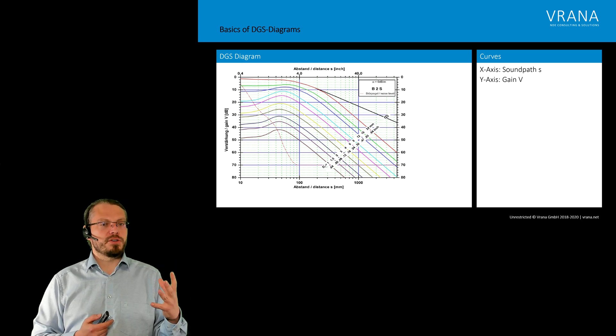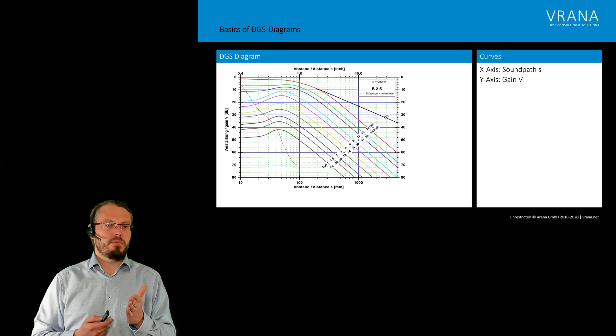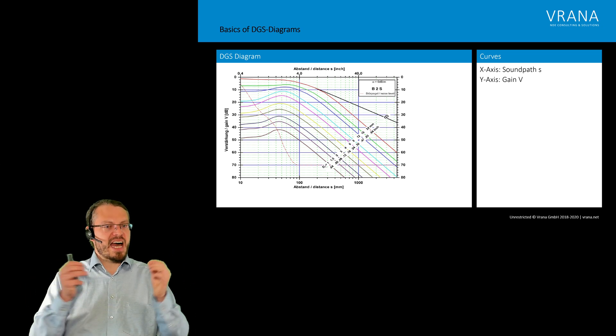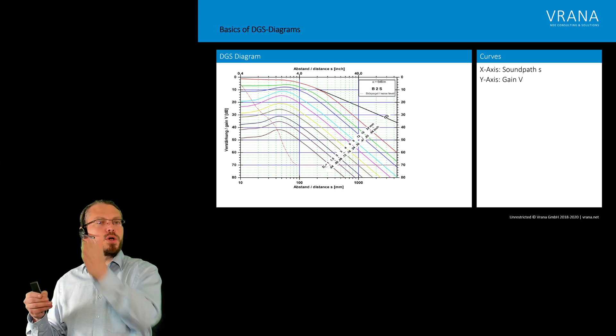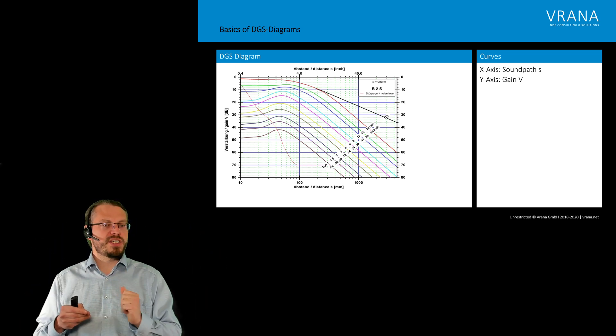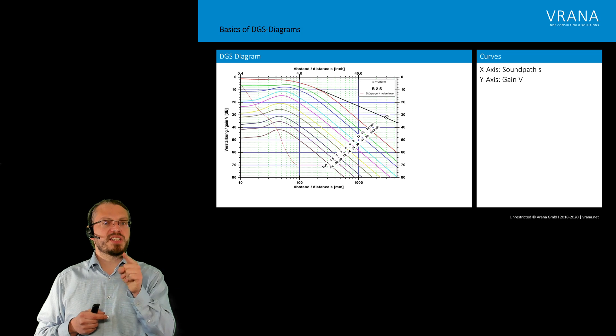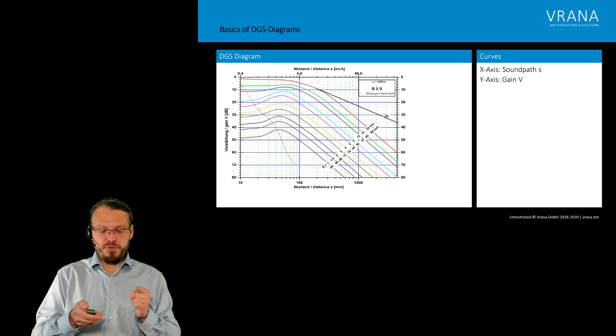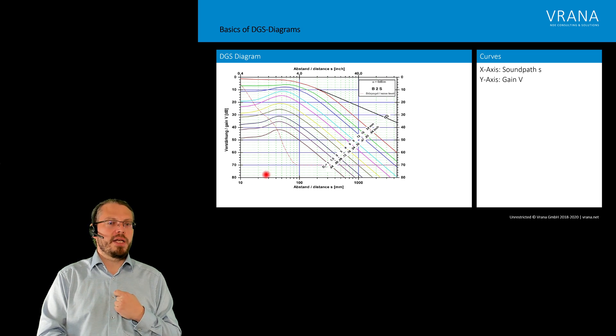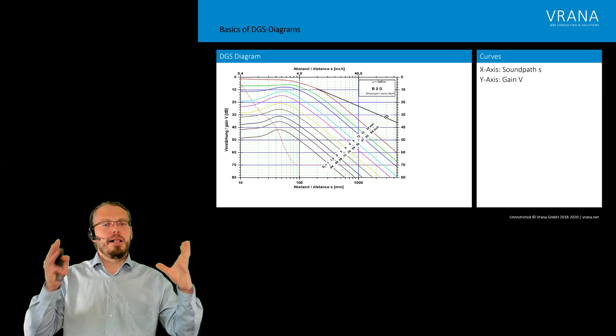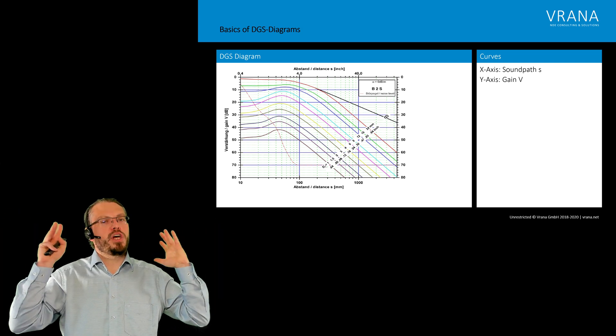Let's have a look at a more modern AVG or DGS diagram, like this one from the so-called B2S probe. On the x-axis we have our sound path. Normally we're used to a linear scale — 10, 20, 30, 40 — but here we see 10, 100, 1000. Looking at the ticks in between: the first tick is 20, then 30, 40, and so on. But the next major tick is 200, then 300, and further along is 2000. This logarithmic scale helps fit a huge sound path span within one diagram.